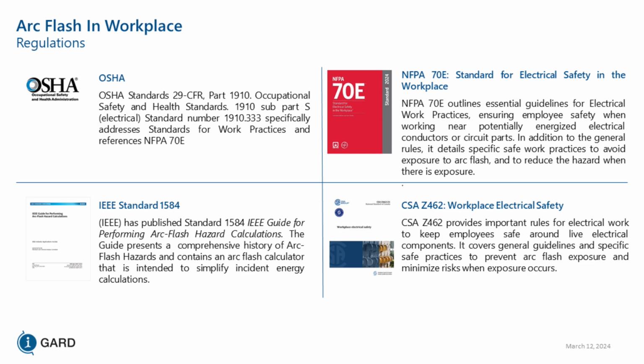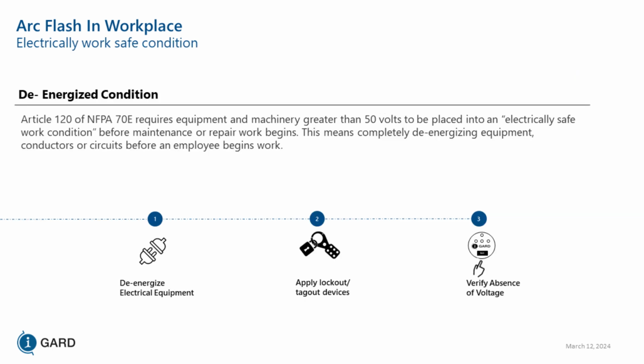ASTM, the standard for testing clothing, has a probability of 50% of preventing second-degree burns if you wear the appropriate PPE. So how well do you want to protect your employees? Are you saying 50% is good or 50% is not a good chance? You want to protect 100% of the arc flashes or 50% of the arc flashes from causing second-degree burns? So these are things that we have to try to balance in the workplace, or making the decision of what to wear to protect the worker. And in Canada, we have Z462. Of course, this is a new code cycle. So the year 2024, we have a new cycle and Z462.